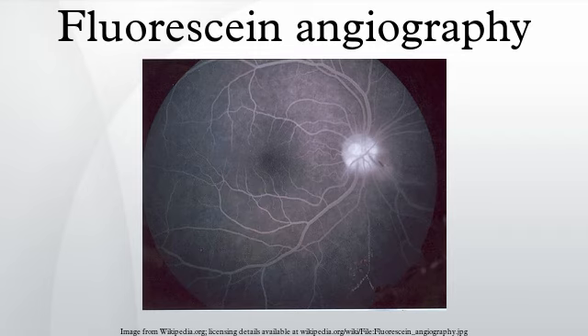The camera may pick up signals from pseudofluorescence or autofluorescence. In pseudofluorescence, non-fluorescent light is imaged — this occurs when blue light reflected from the retina passes through the filter, and is generally a problem with older filters; annual replacement of these filters is recommended. In autofluorescence, fluorescence from the eye occurs without injection of the dye, and may be seen with optic nerve drusen, astrocytic hamartoma, or calcific scarring. Black and white photos give better contrast than color photos, which aren't necessary since only one color is being transmitted through the filter.